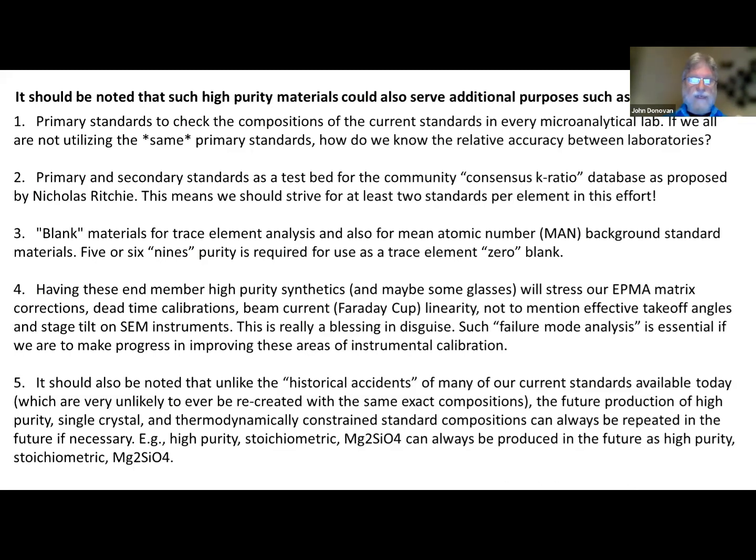It's going to be great for testing our dead time calibrations, our picoamp meter linearity, and the effective takeoff angle on our microprobe or stage tilt on the SEM. This is great. We want to push the instrument and see where it fails, and then we will know the limits of our instrument. And these synthetic materials, by the way, high purity Mg2SiO4 will always be Mg2SiO4. It can be reproduced in the future. It's not like a one-off, like a glass that we can never reproduce again. But these synthetic minerals can be reproduced.